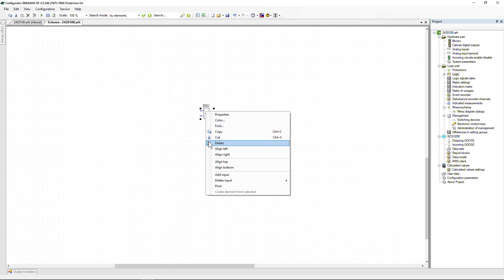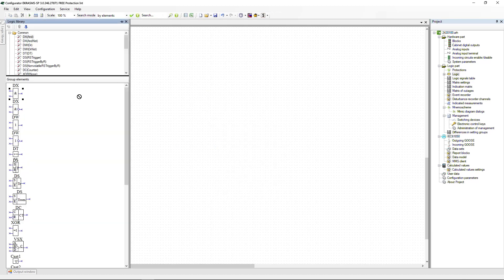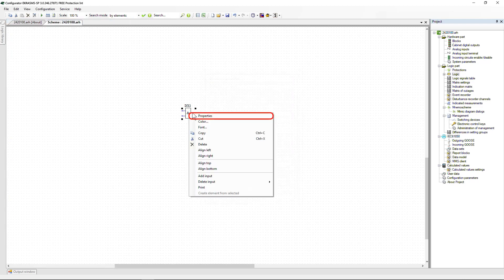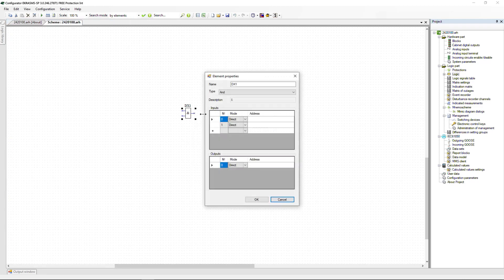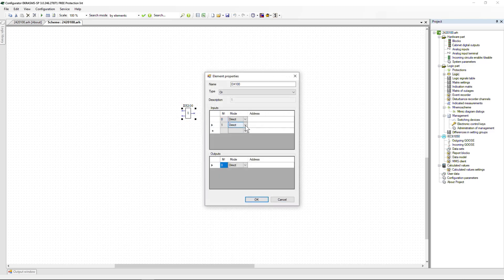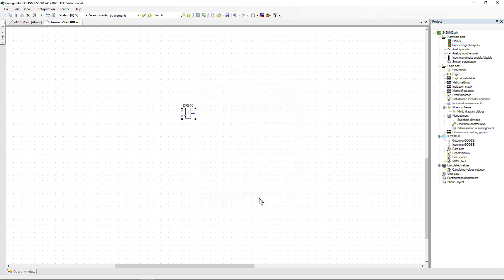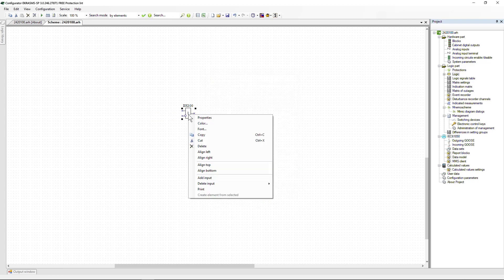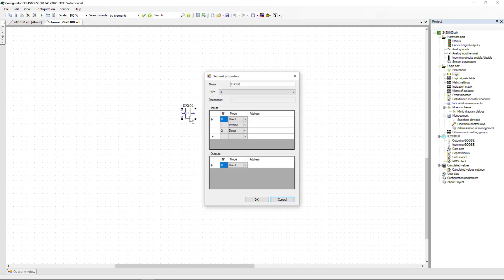The context menu is activated by the right mouse button. The window for setting logic elements is opened by double-clicking the left mouse button or selecting the Properties item in the context menu. In the window that appears, you can specify the name of the element and change its type. To invert the input, select Inverse in the drop-down list of the Mode parameter. Inputs are added via the context menu or in the element properties by specifying the signal address.